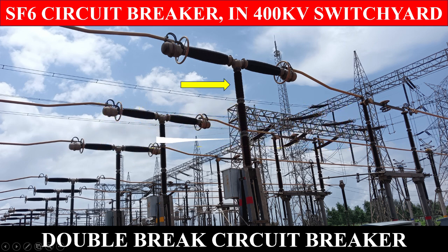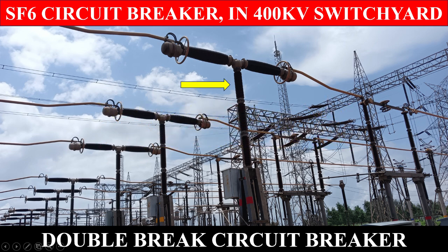4. The closed gas enclosure keeps the interior dry so that there is no moisture problem. 5. There is no risk of fire in such breakers because SF6 gas is non-inflammable. 6. There are no carbon deposits, so that tracking and insulation problems are eliminated. 7. SF6 breakers have low maintenance cost, light foundation requirements, and minimum auxiliary equipment.